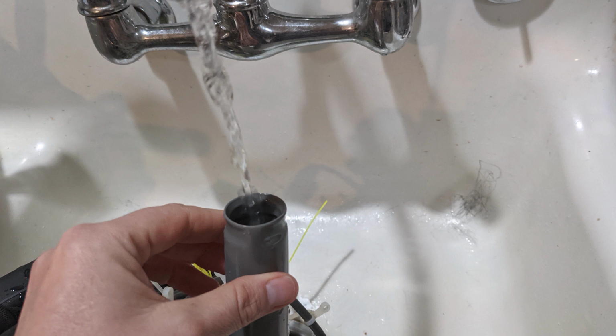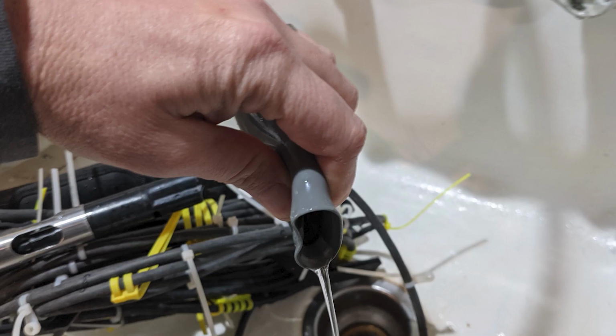If the membrane checks out or if you've replaced it, screw on the guard and add some fresh tap water to the storage chamber. Release any excess water, then attach the chamber. Note, do not use distilled water in the storage chamber as this can cause the meter to fail.